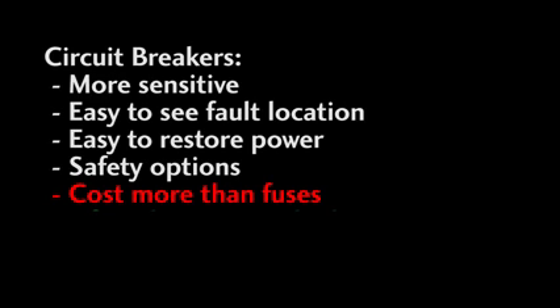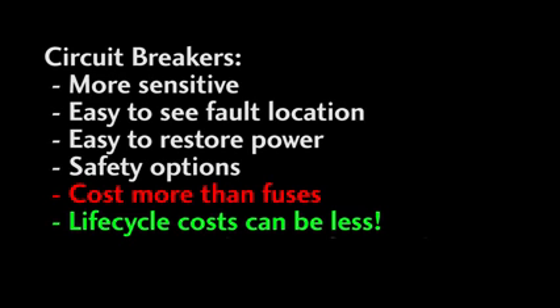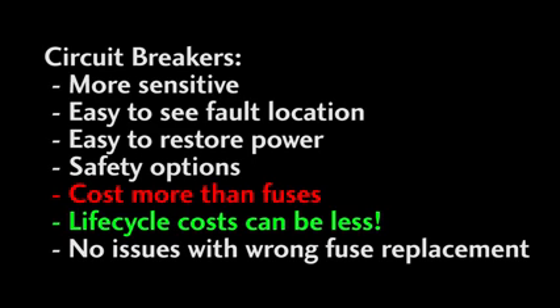The downside of circuit breakers? Well, they cost more to install. But over the lifetime, they can actually be cheaper if you take into account the man-hours spent trying to figure out which fuse blew, equipment lost because it wasn't protected from things like undervoltage, and the cost of the replacement fuses, and more importantly, the time spent finding, ordering, and replacing them. And of course, with circuit breakers, you don't have to worry that somebody put the right size and kind of fuse back in the circuit.